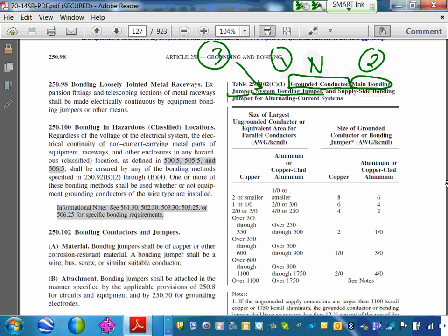I'm sorry, this is system bonding jumper. This is the fancy name for it, supply side bonding jumper, which is number 4. So, system bonding jumper. Now, what the heck is a system bonding jumper? When you have a transformer that you own and operate, and you take a neutral from your transformer and bond the neutral to the ground, that bonding wire is called, instead of main bonding jumper, system bonding jumper. So main and system are identical. Main at the service, you do it right at the service panel. System, you do it inside the transformer that you, as an owner, own and operate, not the utility transformer.